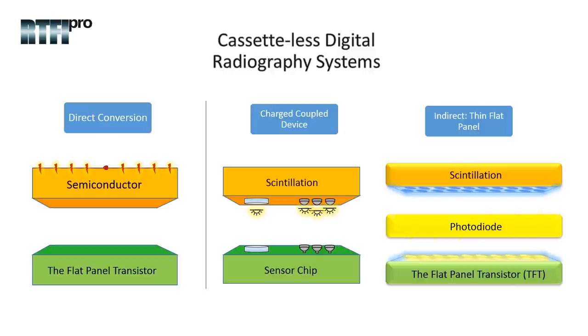In summary, indirect radiography uses a scintillator to convert x-rays into light first and a photon detector converts light into electrons. This method uses amorphous silicon. Direct radiography does not use scintillators as x-ray photons are directly converted into electrons. This method uses amorphous selenium.